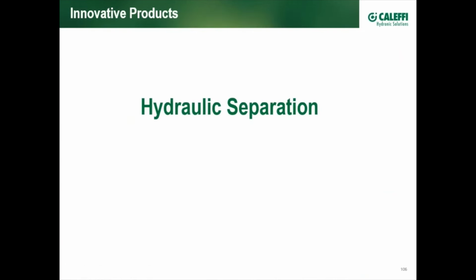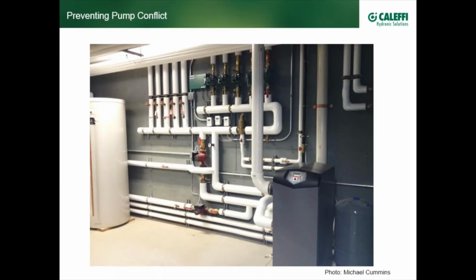Hydraulic separation. What is hydraulic separation? Well, it is basically a way of saying preventing pump conflict. And what is pump conflict? It's when one pump turns on and it creates a back pressure against another pump in the system somewhere. So if we look at this job, if these four pumps over here were on and this one was off, and if this one turned on, by having hydraulic separation, it doesn't allow any back pressure to take place against any of these other pumps.